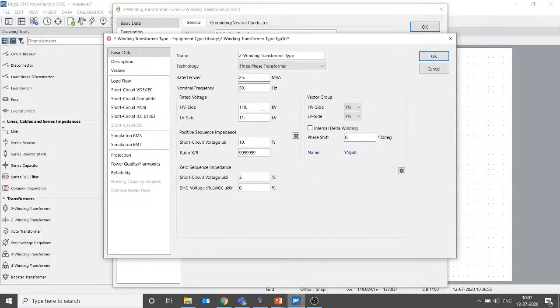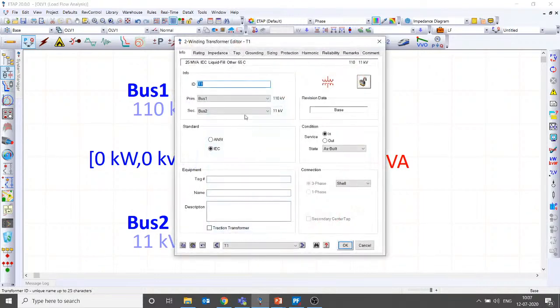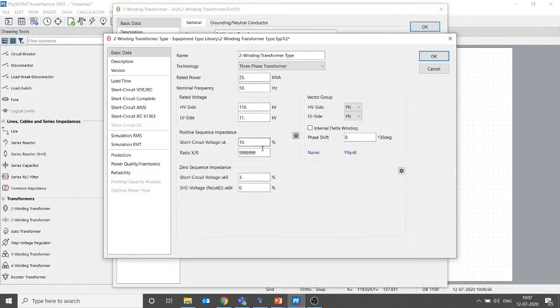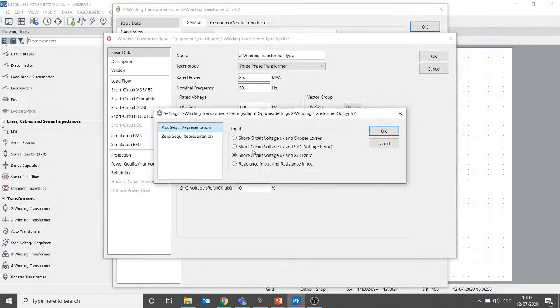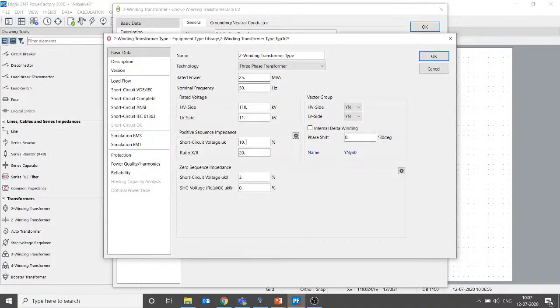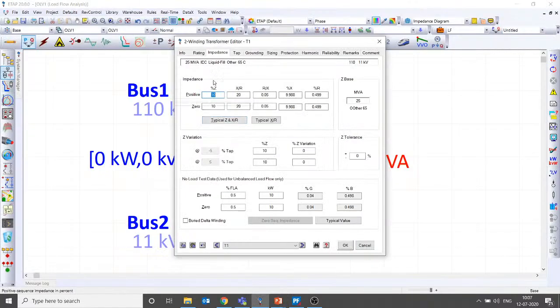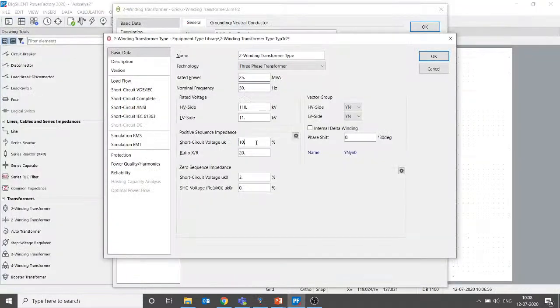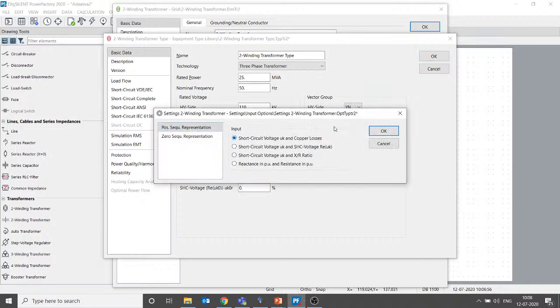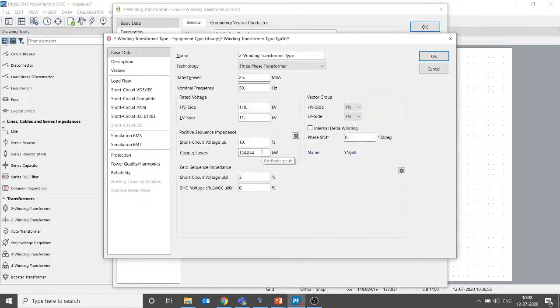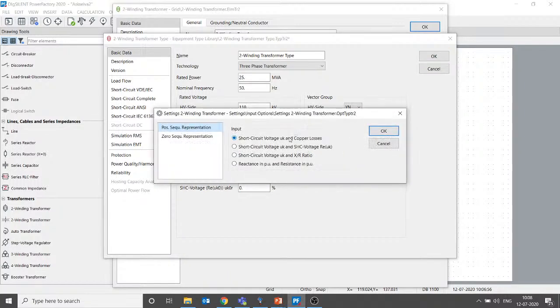So if I just want to match apple to apple with the ETAP results, I can give an X/R ratio of 20. But DIgSILENT allows me to give this parameter in 4 different ways, whereas ETAP gives only one option. In ETAP, you can give percentage Z and X/R. That's the only way you can give the data. But in DIgSILENT, if you have the percentage impedance and the copper loss, you can directly feed that, like 124 kilowatt which is there in the measured data. So DIgSILENT gives about 4 options, but ETAP doesn't offer anything.